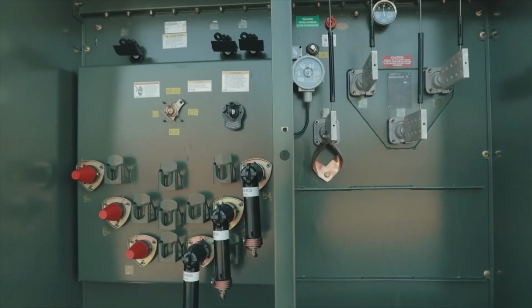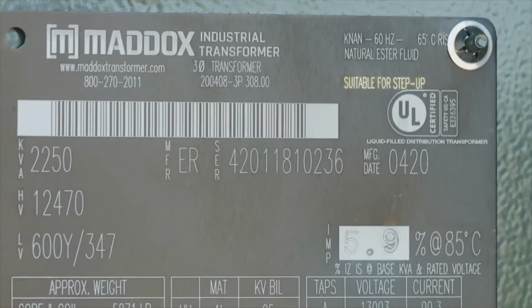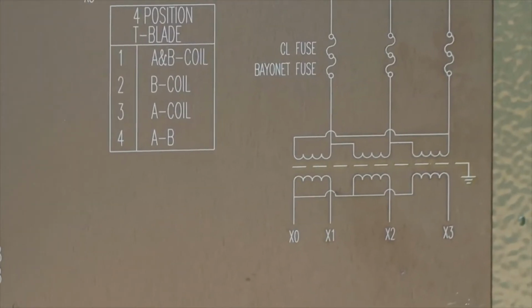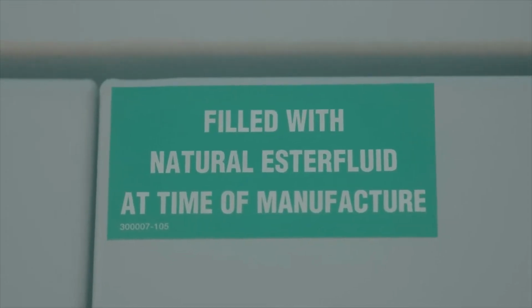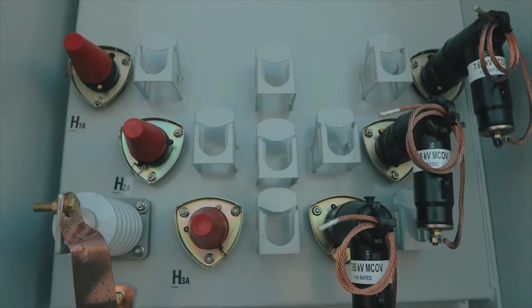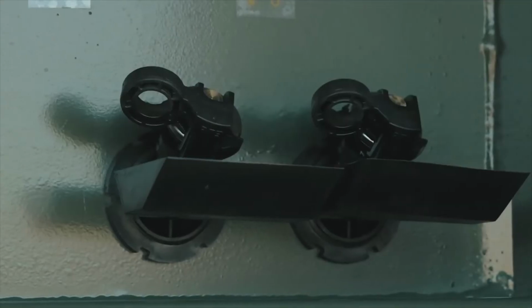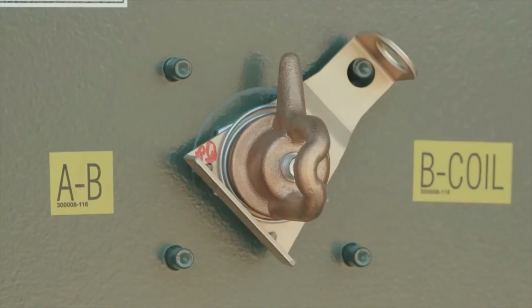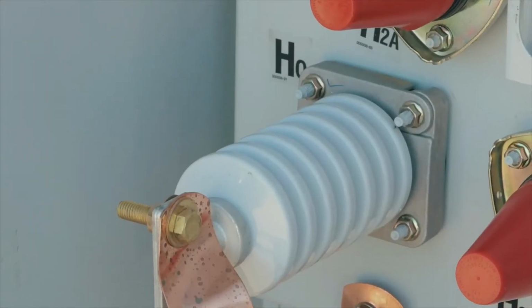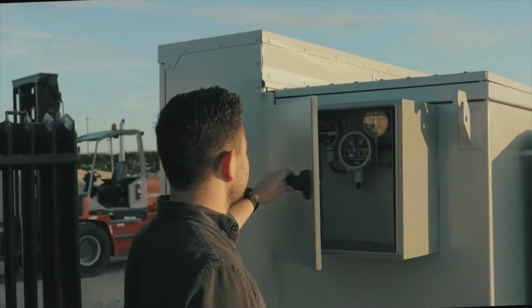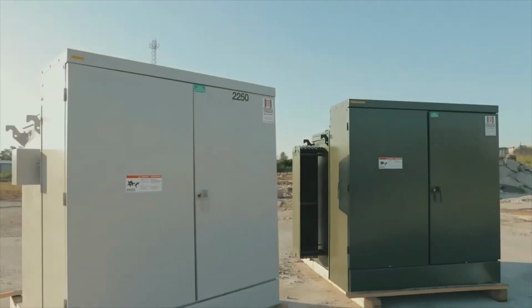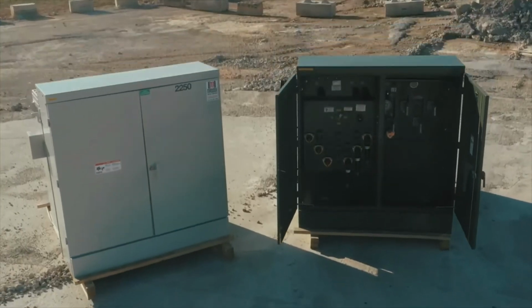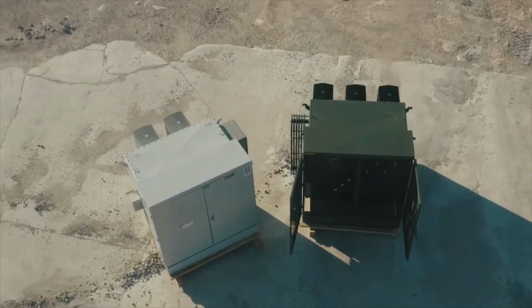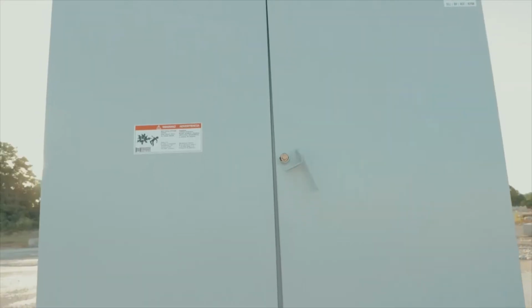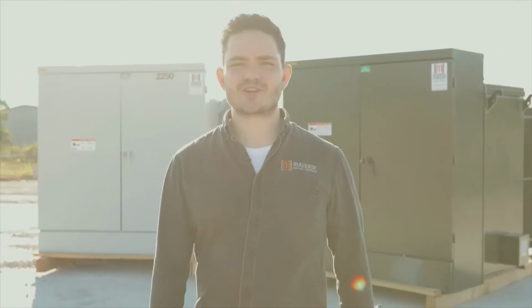Our solar duty pad mounts are suitable for step-up operation and come with features such as electrostatic shielding, biodegradable FR3 fluid, YY connected windings, current limiting fuses, LBOR switching, separated neutral bushings, and many more. Maddox is committed to delivering the highest quality transformers available on the market with half the industry standard lead time to help you meet your critical milestones. Maddox solar duty pad mount transformers truly are designed with solar in mind.